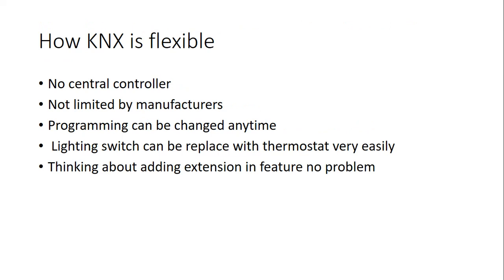KNX is flexible: no central controller, and each device is independent. It's not limited by manufacturer — there are hundreds of manufacturers and you can mix devices from different ones. For example, you can use a thermostat from one manufacturer and a push button from another and they will all work together. Programming can be changed anytime — if you programmed a master bedside switch to turn the whole house on and off, and later you want to exclude the dining area, no problem, you can change it.